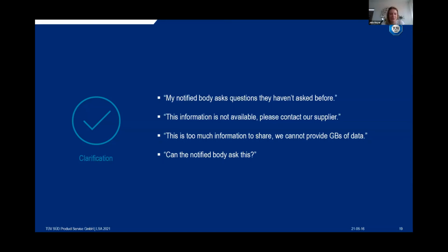The information is not available with me. Please contact our supplier, he's doing everything. That is, of course, also not a proper situation for you as manufacturer. You as legal manufacturer are legally responsible for your product, and also for all the information from your supplier, to make sure that you have a safe device. So the notified body is not going to any kind of subcontractor or supplier first. He's going to you and asking you for the information, and he will then audit the supplier to see if that is working as intended, but he is not individually contacting suppliers.